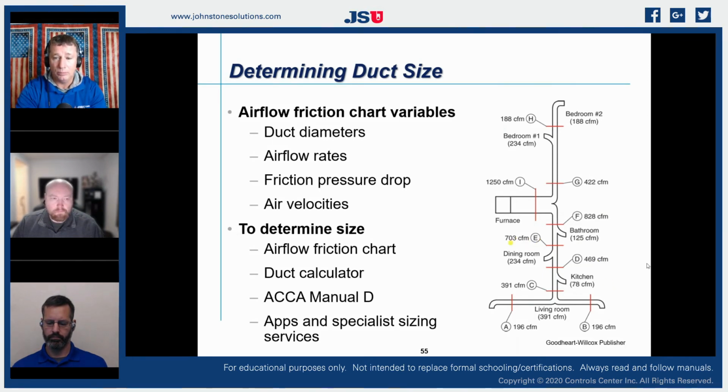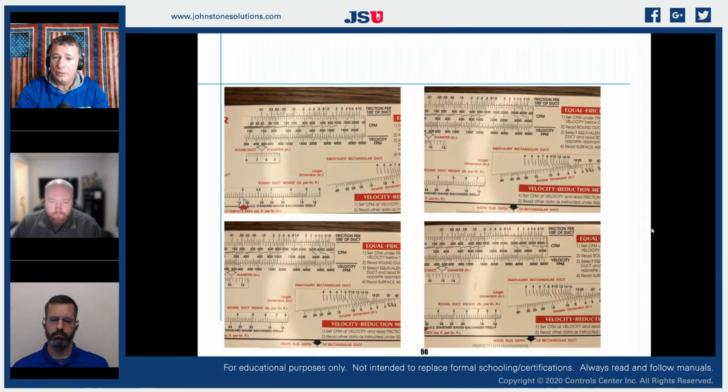So now I can plug that number in. I can plug my 703 in at 0.1. 703 at 0.1 is going to allow me to run an 8 by, it's over 14, so it's actually going to have to be a 16, which means at that point I can drop down to an 8x16. See, the whole purpose of doing proper duct sizing is that we maintain the static pressure through our entire system, and we also minimize the amount of sheet metal that we do in our construction.